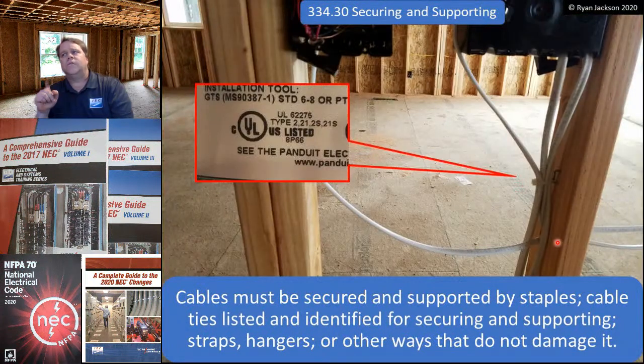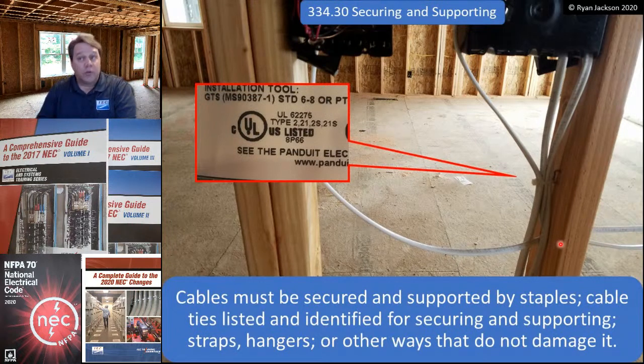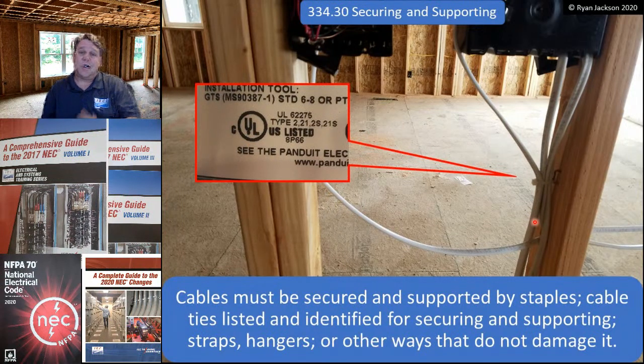When it comes to using cable ties, they added some specific text in the 2017 code. Support hardware does not need to be listed. However, cable ties for support hardware do need to be listed. There's cable ties and then there's cable ties. You guys have probably all installed cable ties that are junk. You're just tightening the cable tie and they break. Well, look, if you want to put that under your desk or behind your TV, fine. You're not going to use that to support the wiring of a building.